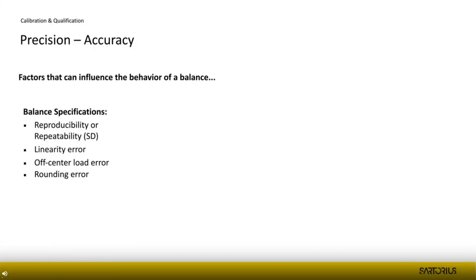Let me start with the balance specifications. The key concepts are reproducibility or repeatability, linearity error, off-center load error, and rounding error. These can also be seen in general metrology. When we have legal metrology related to the World Trade Organization or OIML — legal-for-trade instruments — we talk about maximum tolerated errors, and the instrument is tested for those as a legal verification.